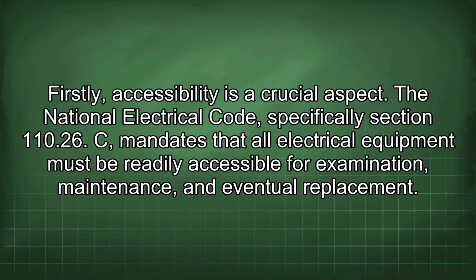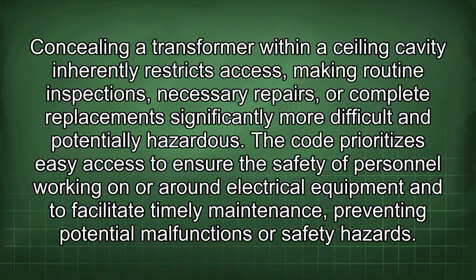Firstly, accessibility is a crucial aspect. The National Electrical Code, specifically Section 110.26(c), mandates that all electrical equipment must be readily accessible for examination, maintenance, and eventual replacement. Concealing a transformer within a ceiling cavity inherently restricts access, making routine inspections, necessary repairs, or complete replacements significantly more difficult and potentially hazardous. The code prioritizes easy access to ensure the safety of personnel working on or around electrical equipment and to facilitate timely maintenance, preventing potential malfunctions or safety hazards.